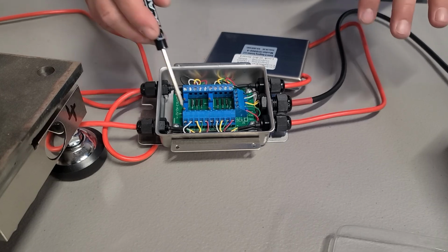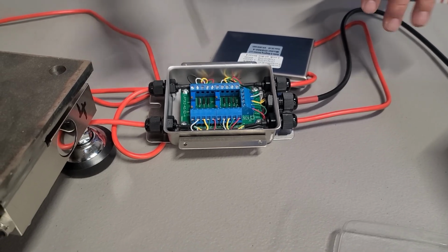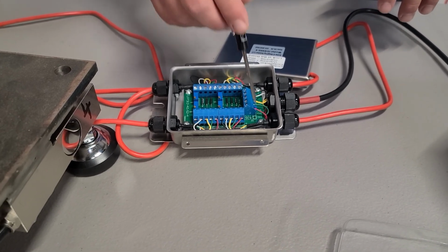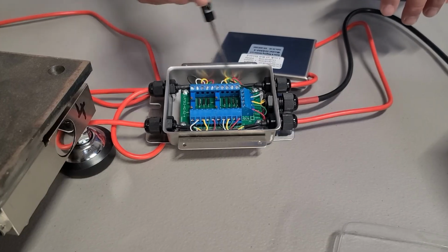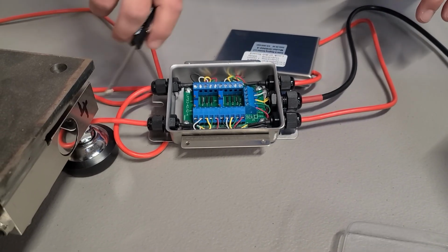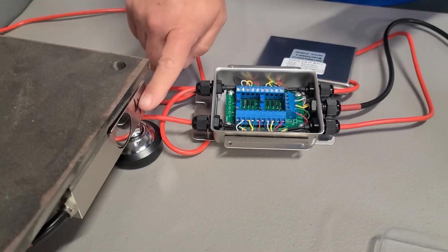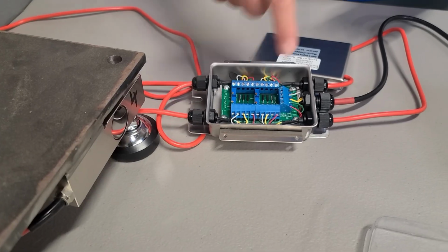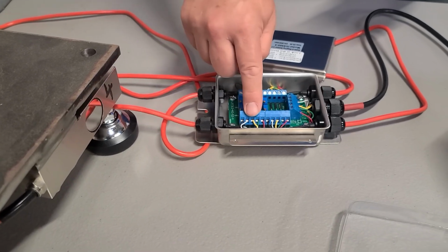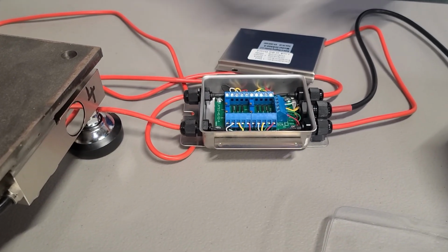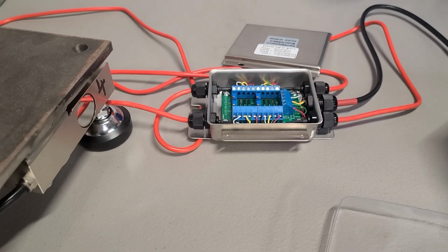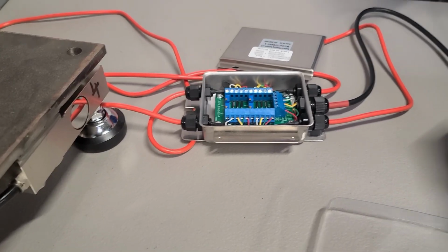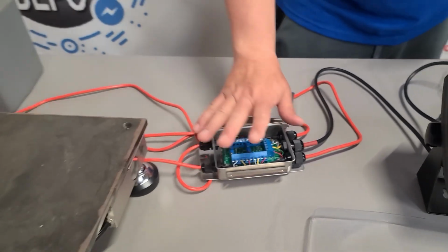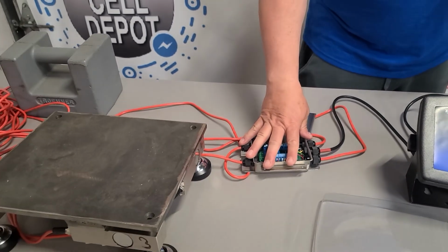The only thing that you're going to connect is the load cells, the 4 load cells. And if you take a look at the card, it actually tells you 1, 2, 3, 4. So when you mount the load cells, you can number your load cells to the terminal, as you can see. Now, after you've done that, you've assembled your base, you've worked on your summing card.